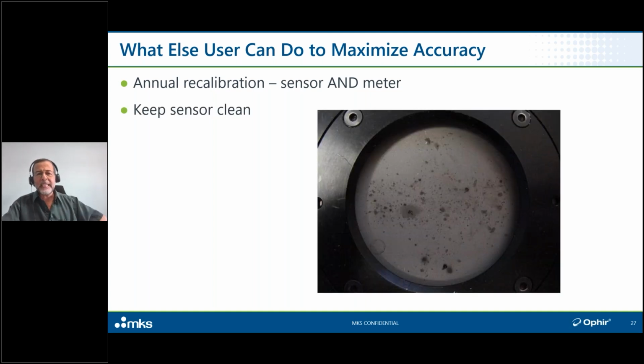You want to keep your sensor clean. What you're looking at here is a thermal sensor that at some point must have had some kind of organic contaminant splashed onto it. Had the user then cleaned it off, following the recommendations that every manufacturer will give for the particular sensor in question, in this case a simple soft tissue that's standard in every optics lab, and a simple solvent like acetone or ethanol or something like that, it would have been cleaned off very easily. But in this case, it wasn't cleaned off, and the next exposure to a laser beam burned it on. There's no way to get that stuff off now. This sensor is going to need a relatively expensive disc replacement. Prevention is always better than repair.